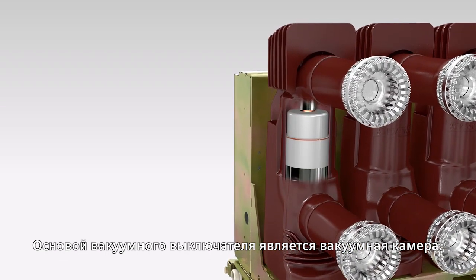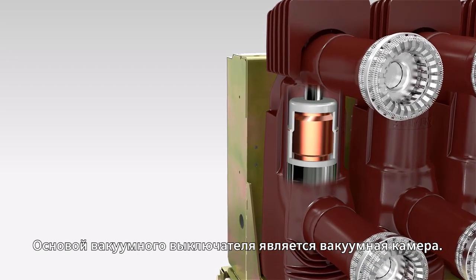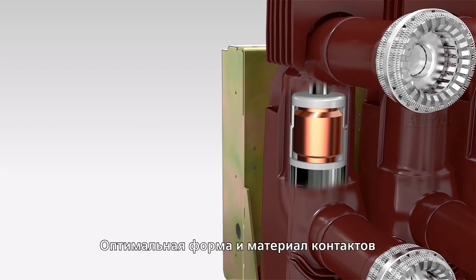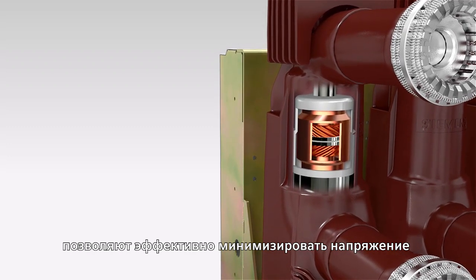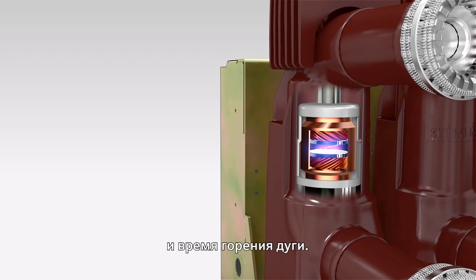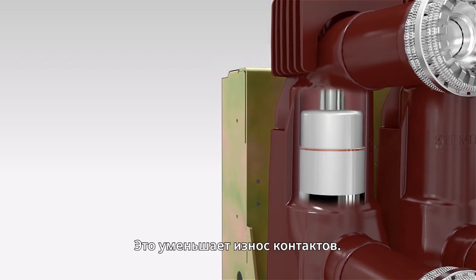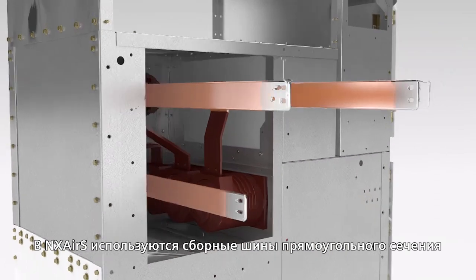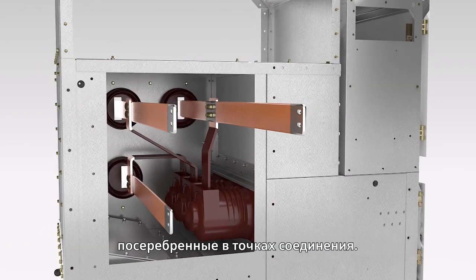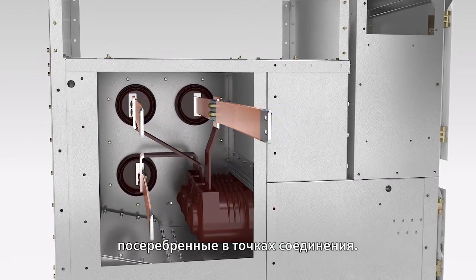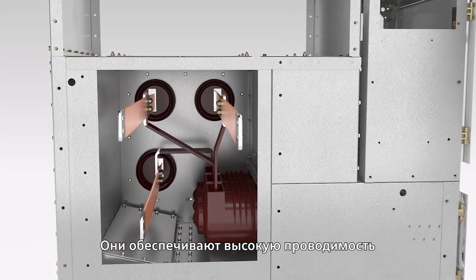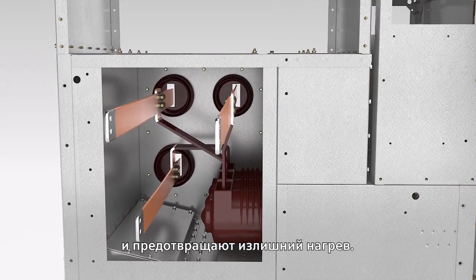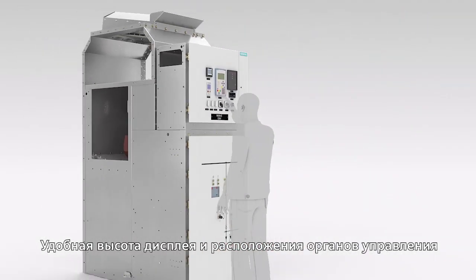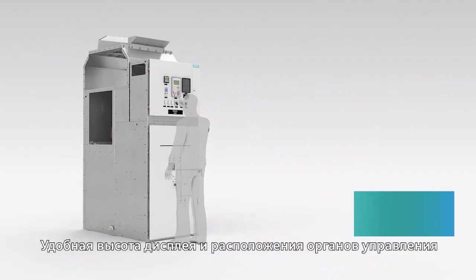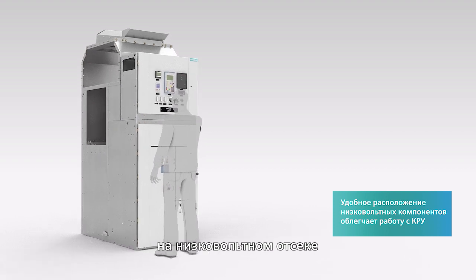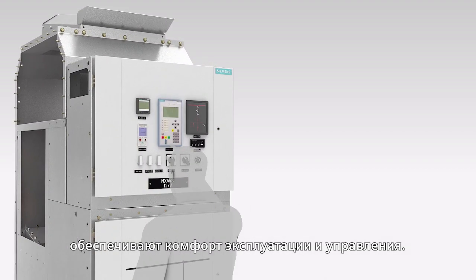The vacuum interrupter is the core of a vacuum circuit breaker. The optimized contact shape and material can minimize arcing voltage and arcing time effectively. This reduces the contact wear. NXAirS applies rectangular bus bars and the connection areas are silver plated. It ensures a high conductivity during the entire life cycle and prevents excessive heating. Proper height of the display and conveniently situated operating positions of the low voltage compartment make the operation and control comfortable.